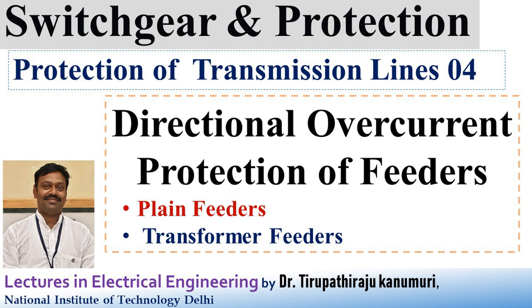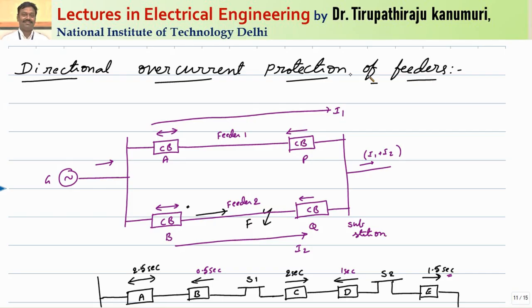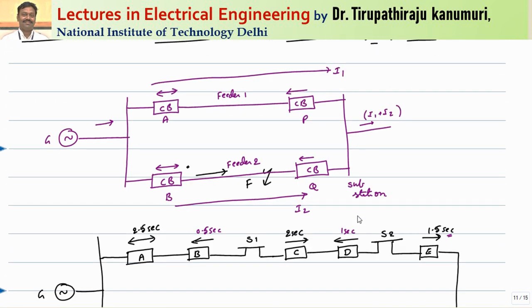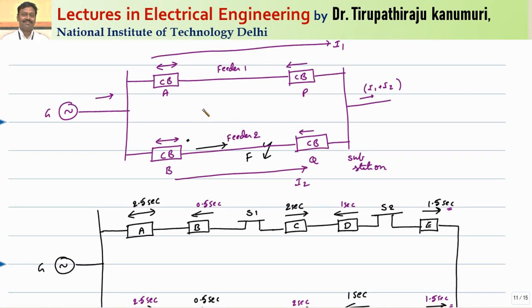Hi y'all, today we are going to discuss about directional overcurrent protection of feeders. In the last class, we have seen the different types of protection - time graded protection - for the case of parallel feeders as well as for ring mains. There will be non-directional relays used as well as directional overcurrent relays. Generally, these directional overcurrent relays are designed in such a way that they will operate only for a particular direction of a fault.